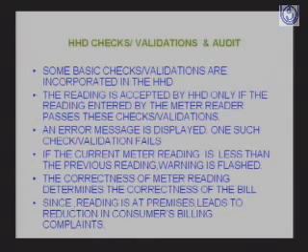Now there are certain checks and validation checks in storing, downloading or uploading the data in the handheld device. Some of the basic checks which are required for validation are incorporated. For example, the next day reading should not be less than the previous day reading. Now there are two issues here. First, the meter reading for billing purposes, which is once in a month. Second, the meter reading for audit purposes, twice in a day, to check the problems which are there.